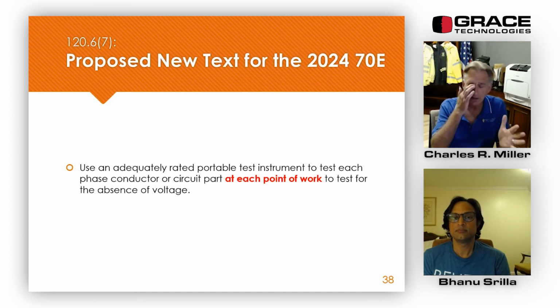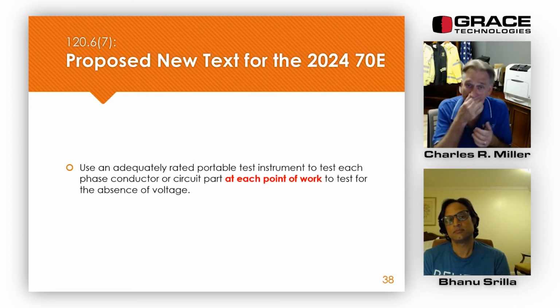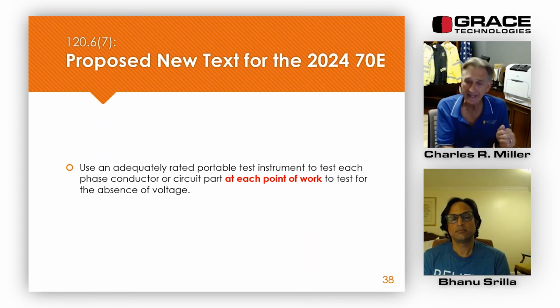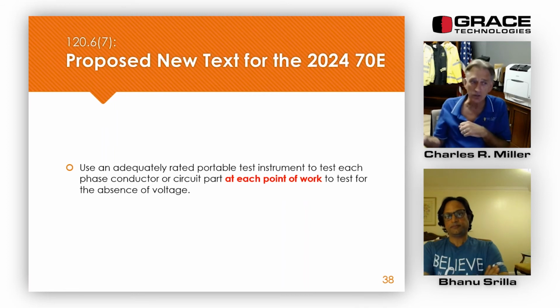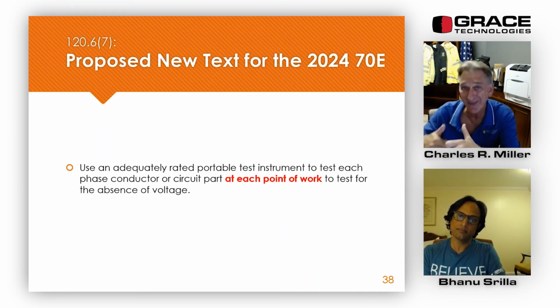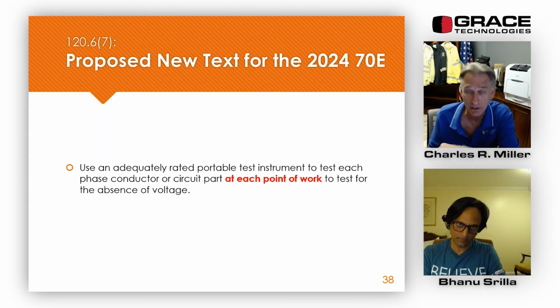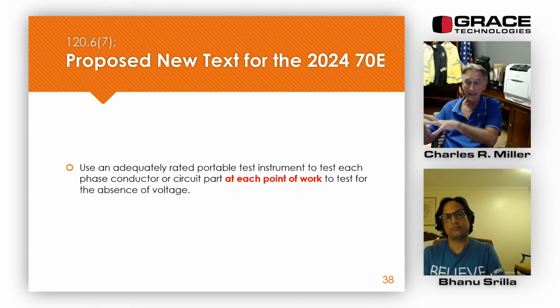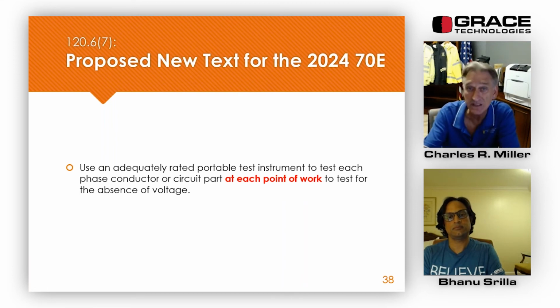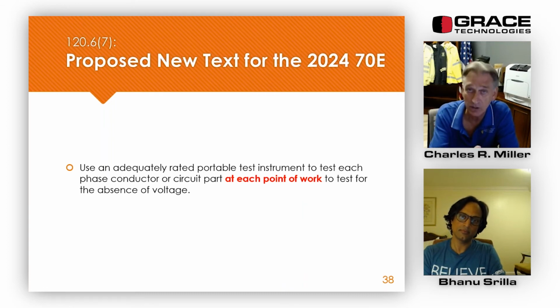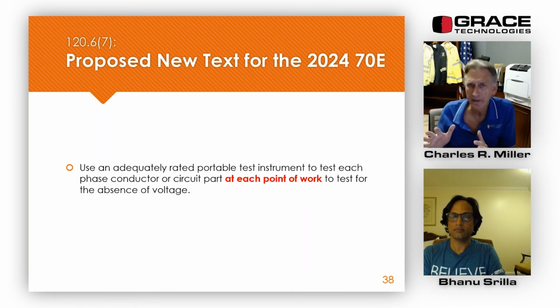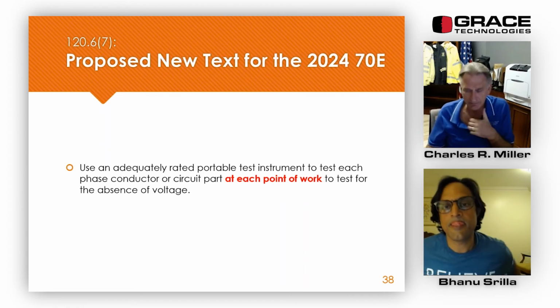Probably the idea for this came from someone turning off a disconnect switch in an MCC, a motor control center bucket, and testing on the load side of the disconnect switch that goes out to a motor. At that point, I would want the absence of voltage to be checked at the motor. Not all remote motors that are far away have a disconnect switch within sight of the motor, because the National Electrical Code says it has to be within sight of the motor unless the disconnect switch can be locked in the off position. So I just see this being a bit of a problem.